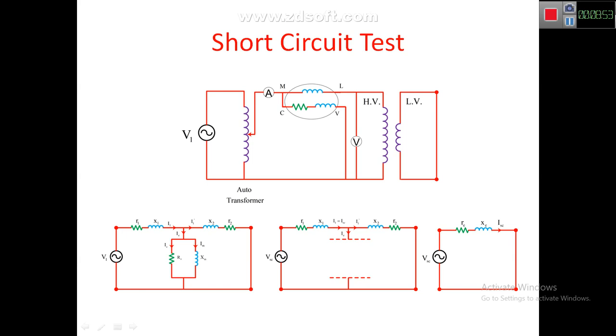The short circuit test is conducted on the HV side, so all instruments are connected on the HV side. The circuit has a voltage source and an auto transformer to provide the necessary current. Since current is important here, the ammeter is placed immediately after the auto transformer, followed by the wattmeter, and the voltmeter is connected accordingly.